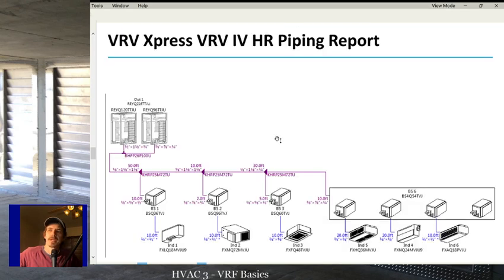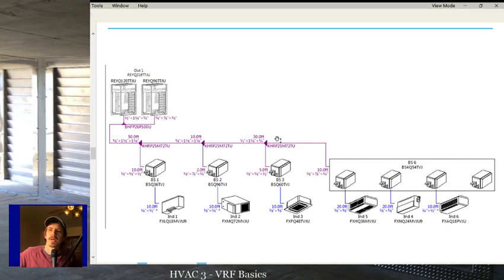So when we're looking at these, just understand that I'm going to talk a lot about Daikins here, but manufacturers can vary and their wiring is different. Mini splits are pretty universal in their wiring. VRF, every manufacturer has a different requirement on its wiring. And then how long your line sets can be, what size the line set has to be joint to joint. All these things have to follow manufacturer's instructions.